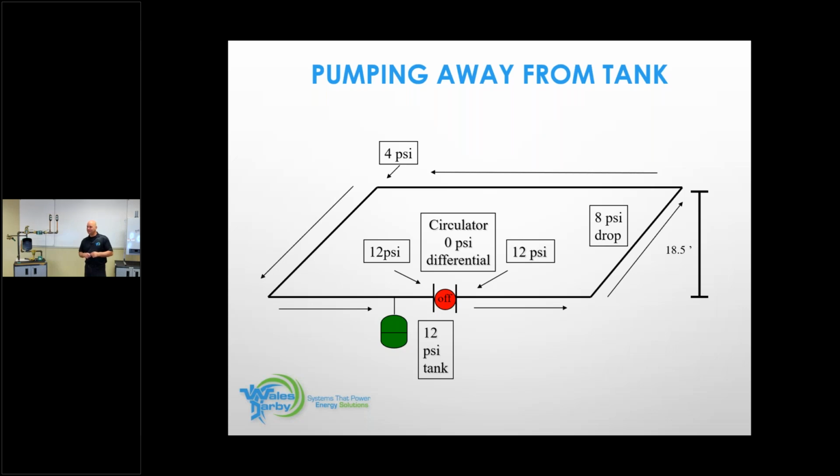Interesting. Okay, one gentleman saying on the back side of the circulator, 0. Yeah, okay, that's not a good thing. That'd be a time to replace the circulator at some point. One gentleman saying everything stays the same. Okay, one gentleman says 1 same, 2 same, 3. I'm thinking that they're all thinking everything stays the same.